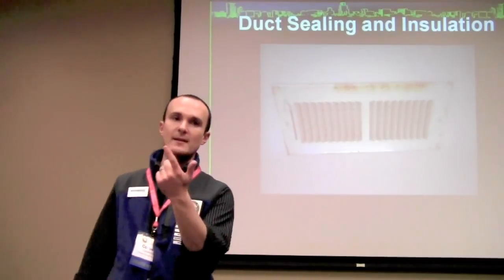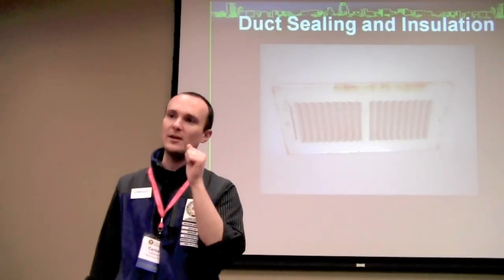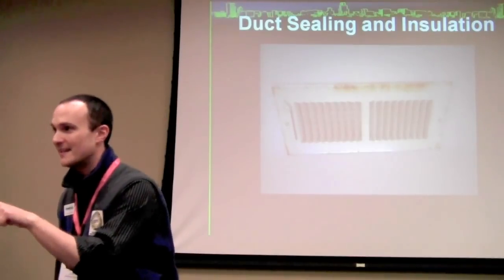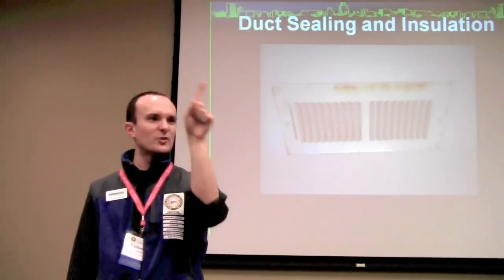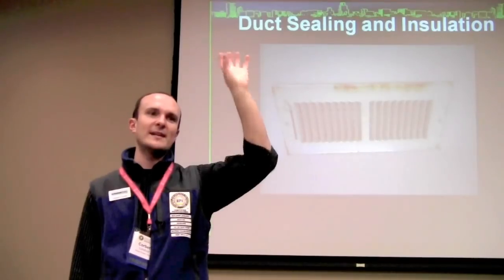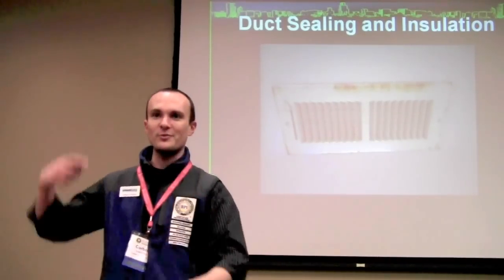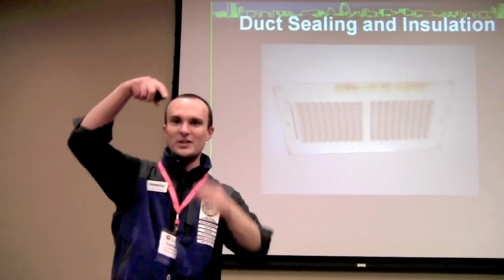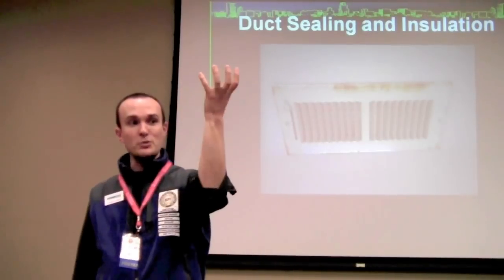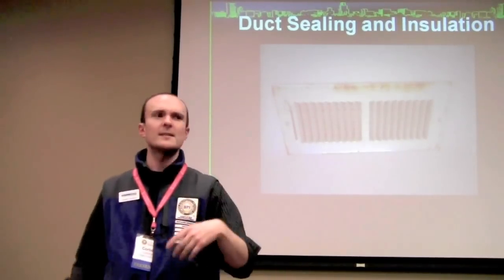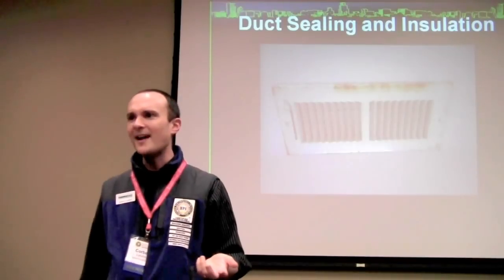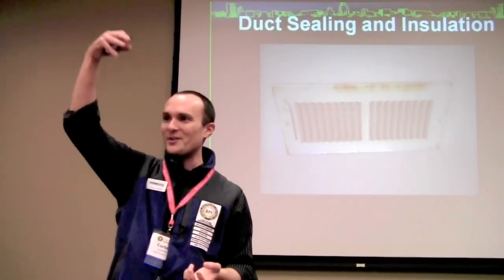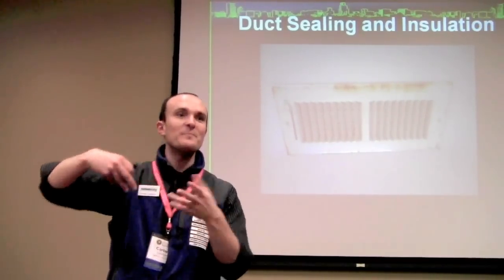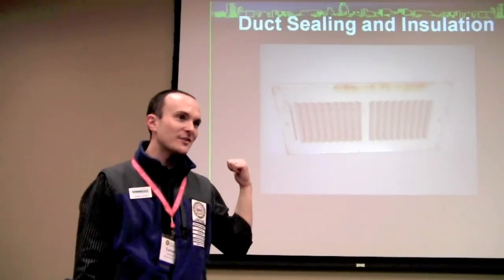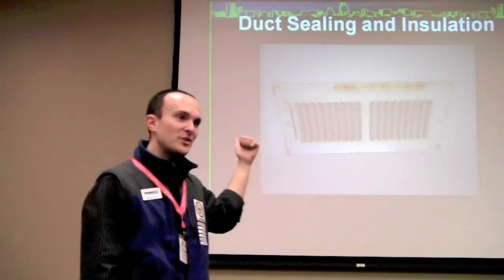In summer season, you'll see brand new houses we get called out to that haven't even been lived in yet, and they've got little stains around the drywall of the ceiling registers. That's because cold air travels through the ducts when the air conditioner's on. It's going to be about 55 degrees on that metal at the boot. The boot is uninsulated because it's not considered important to insulate the boot — who cares about that, right? And hot, moist, 130-degree attic air is in contact with that boot. It condenses, stains your drywall, and rots out your register covers.